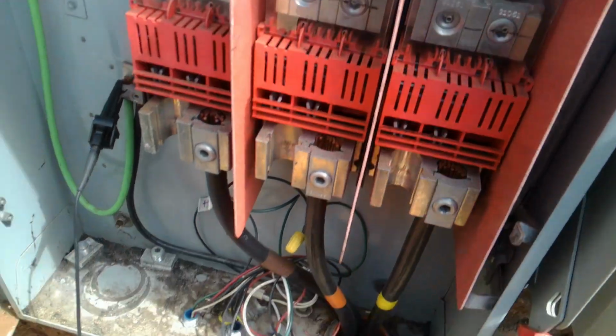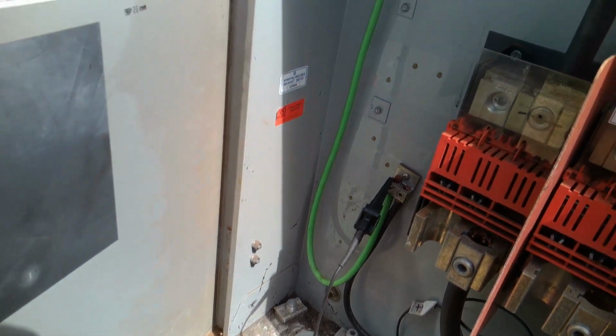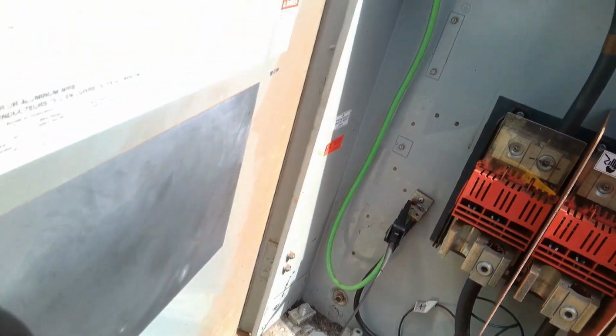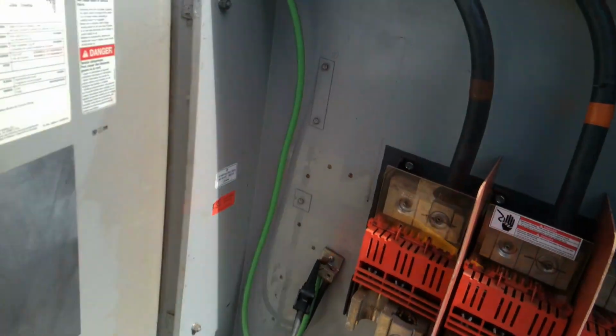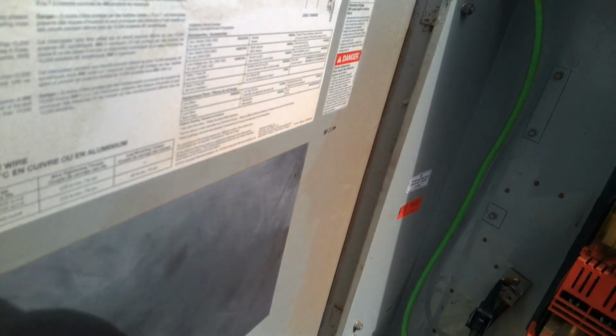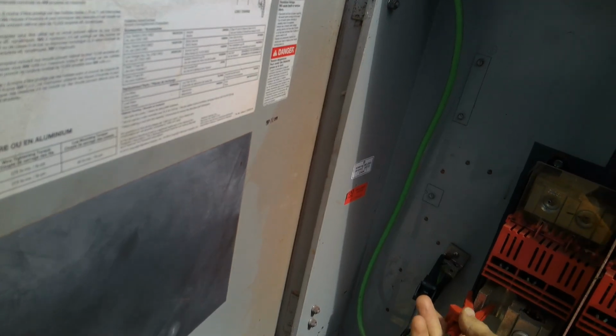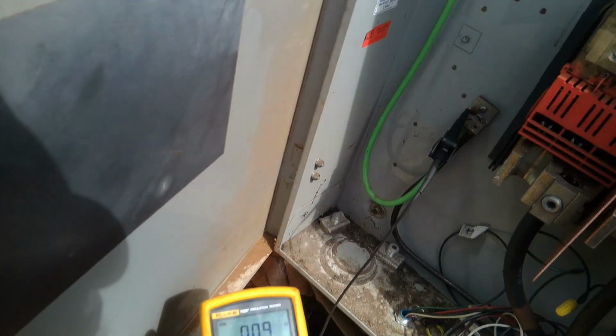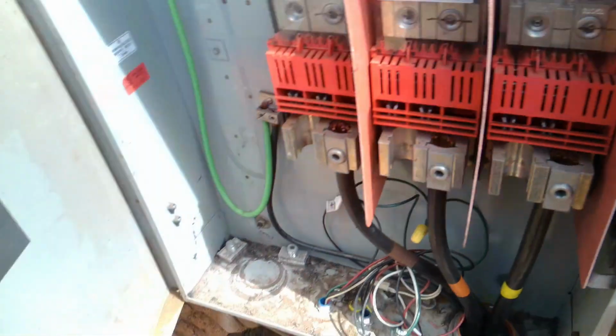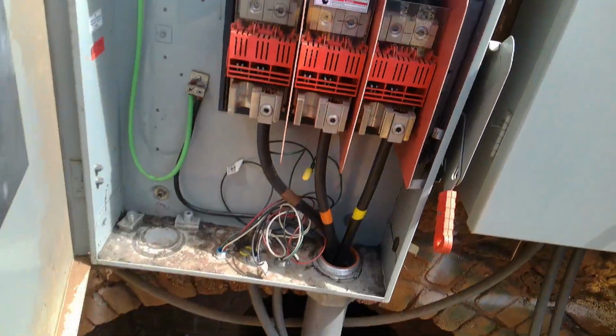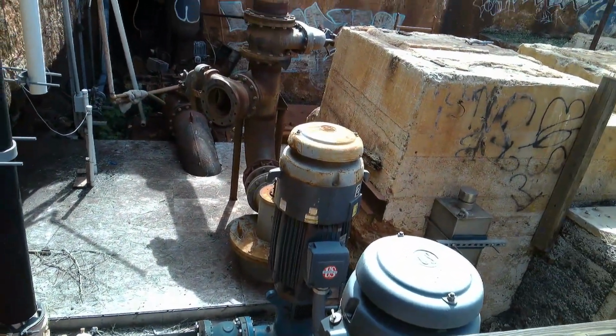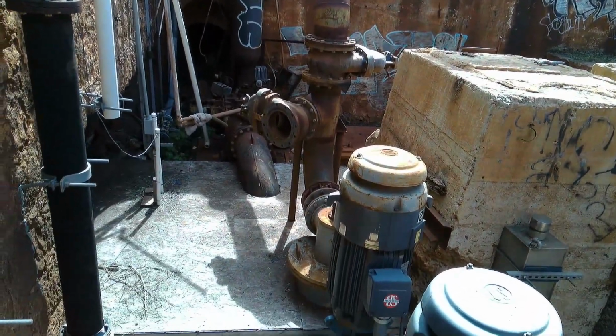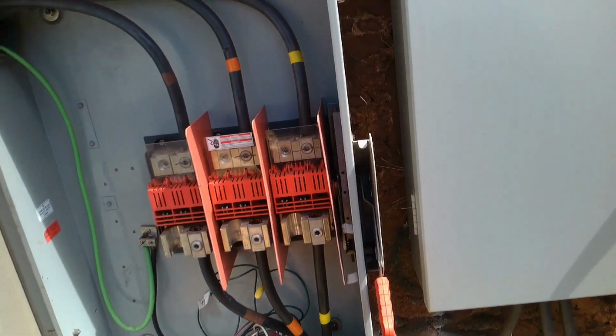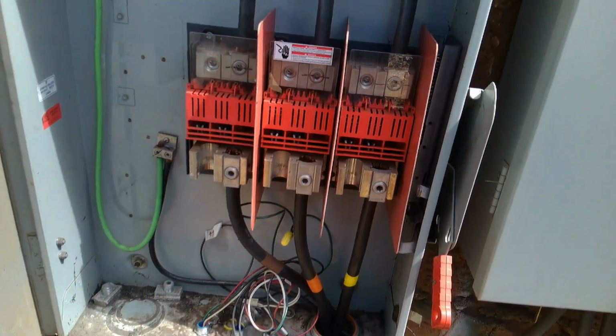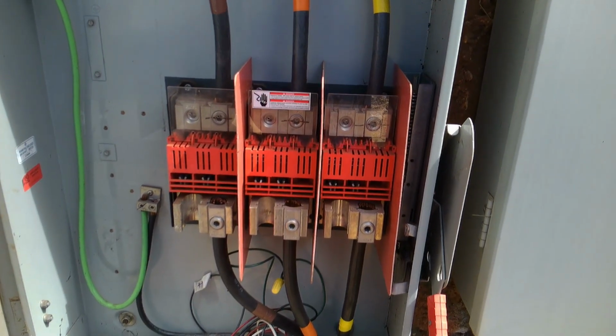Okay, well, either way, let's drop down our scale. It is showing 0.12 ohms to earth on line 3. 1/10 of an ohm to earth on line 2. It's also showing low battery. And 0.8 ohm to earth on line 1. I am flabbergasted by that, and I'm going to go get my other meter to verify it with, because that would mean that there's a dead short in pump 2, like a dead short. And that would also mean I've been kind of wasting my time, perhaps, with this power filter stuff. I should still follow up with them.